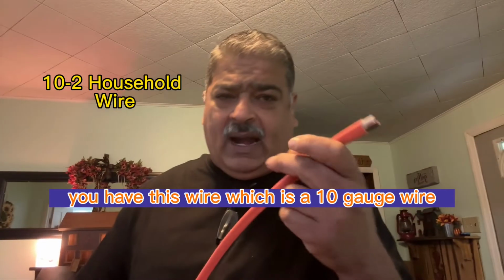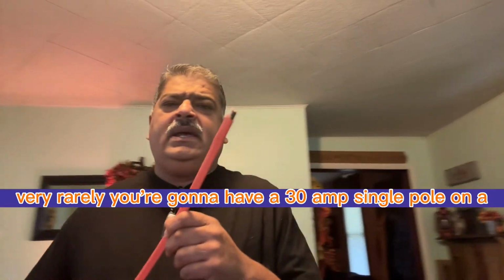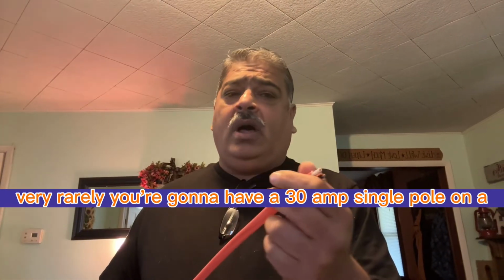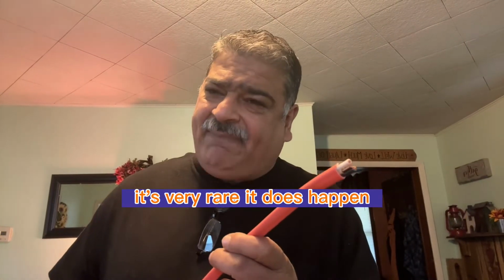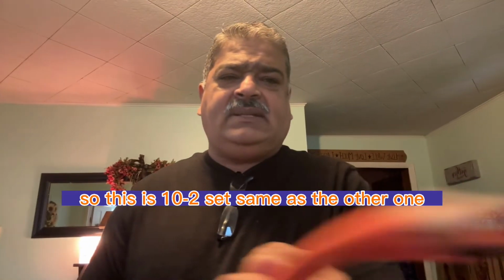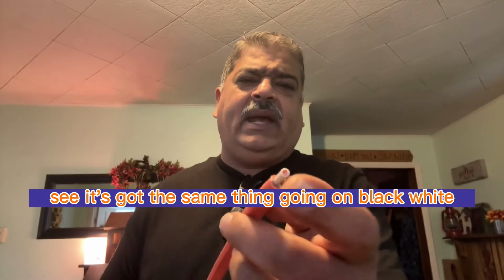Now, you have this wire, which is a 10 gauge wire. Very rarely you're gonna have a 30 amp single pole on a 120 volt circuit on a 10 gauge. It's very rare. It does happen, but it's very rare. So I'm not gonna really talk about it. So this is 10-2, same as the other one. See, it's got the same thing going on, black, white.